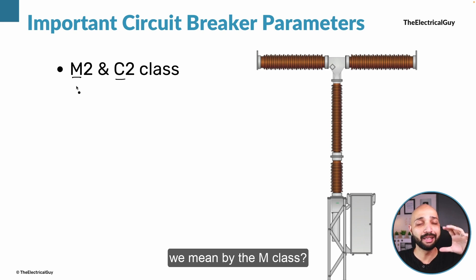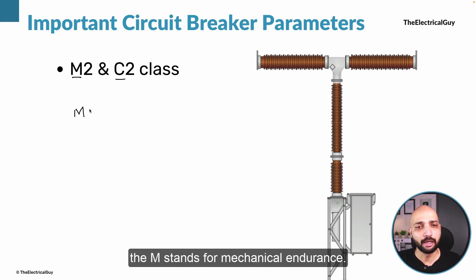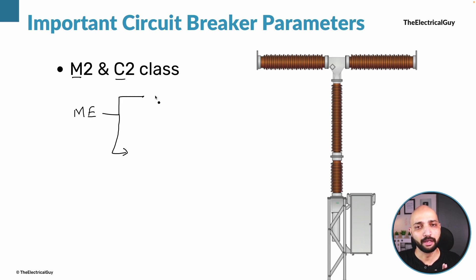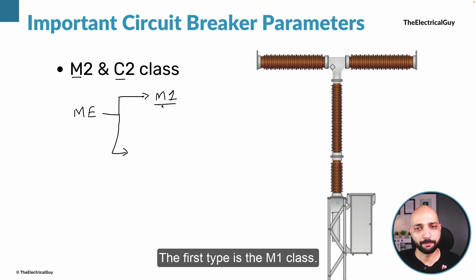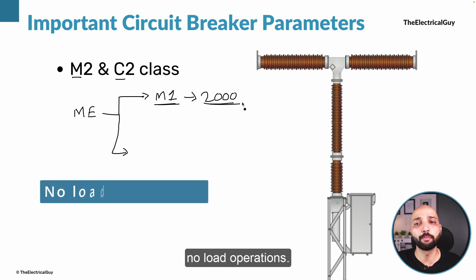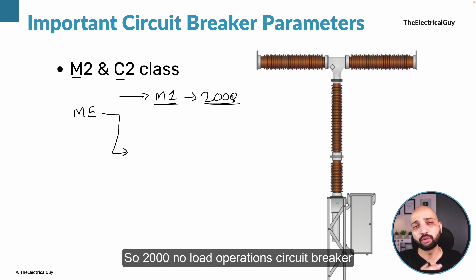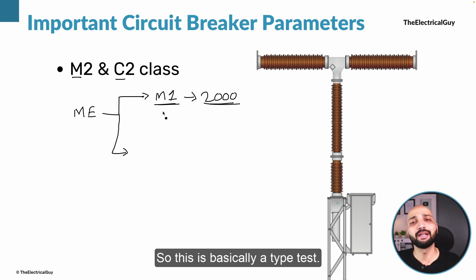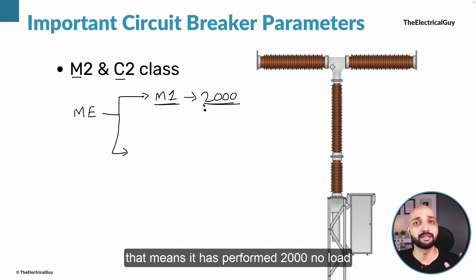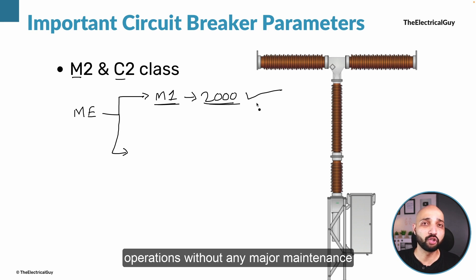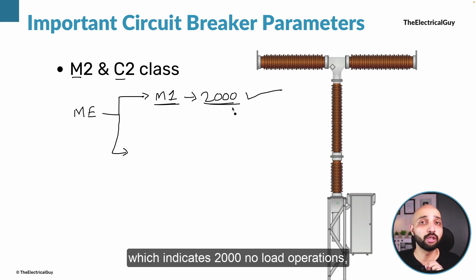Let us first start by understanding what is M2 and C2 class. The M stands for mechanical endurance class. As per IEC, this mechanical endurance class is divided into two types. The first type is M1 class, which means the circuit breaker needs to perform around 2000 no-load operations without having any major maintenance during testing. So this is basically a type test.